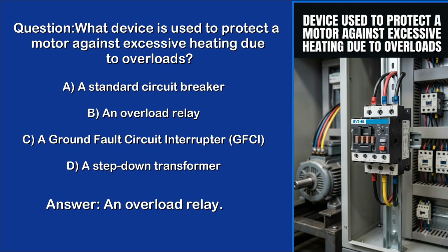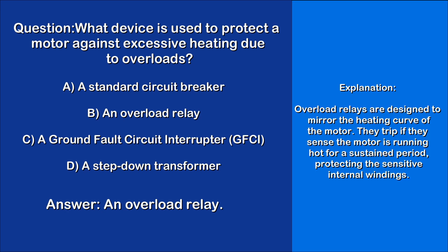Answer. B. An overload relay. Explanation. Overload relays are designed to mirror the heating curve of the motor. They trip if they sense the motor is running hot for a sustained period, protecting the sensitive internal windings.